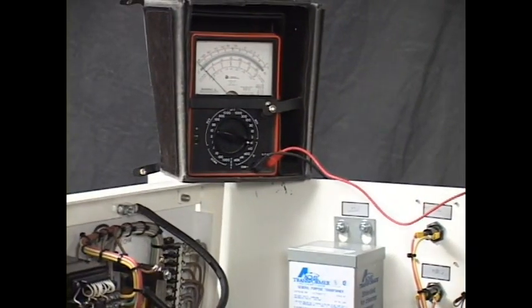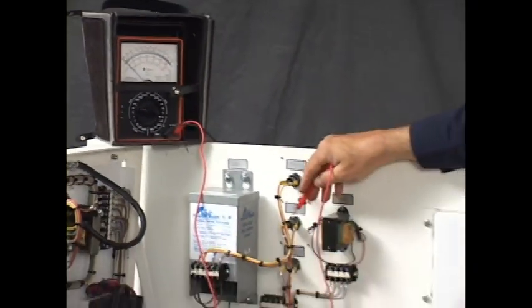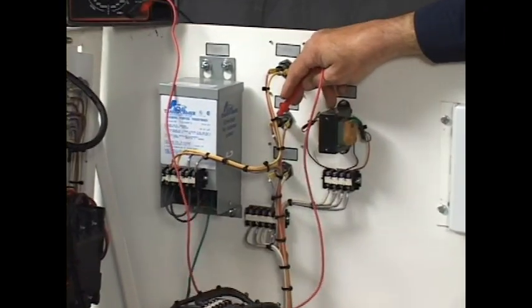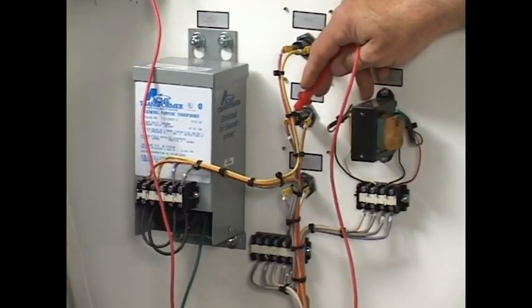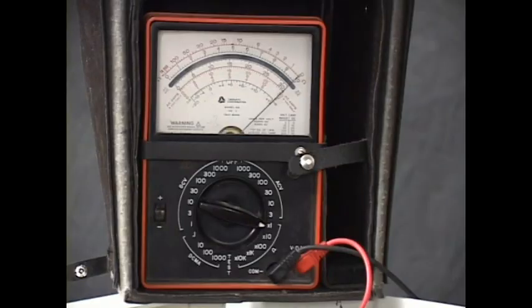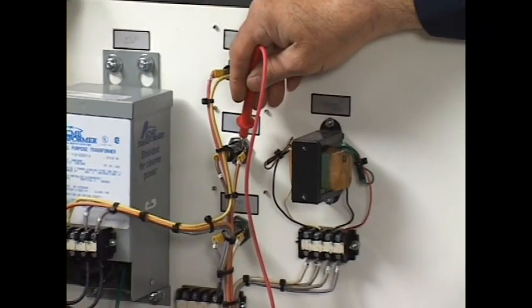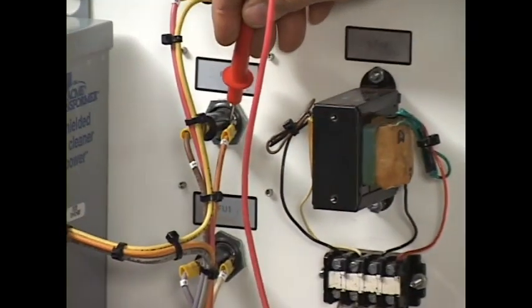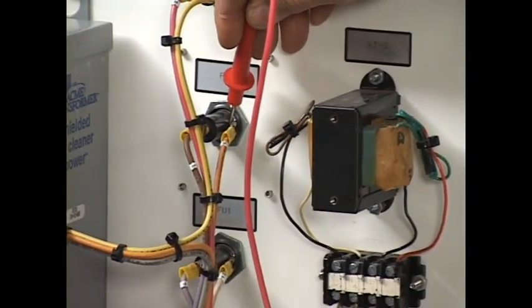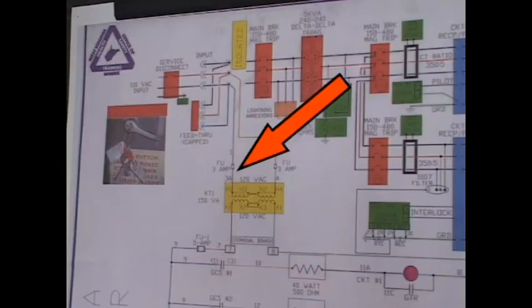The first point that I can check is wire 1 to the line side of the fuse. Wire 1 is intact, as the needle indicates by going all the way to 0. There's no resistance. Go through the fuse to wire number 3, the other side of the fuse, the load side of the fuse. As you see on the drawing, that's this point right here. The only thing I've added to the circuit is the fuse.